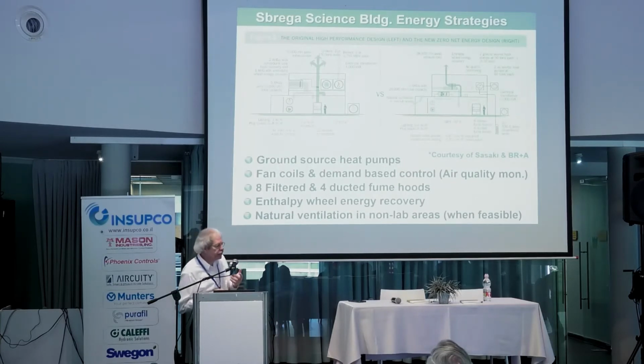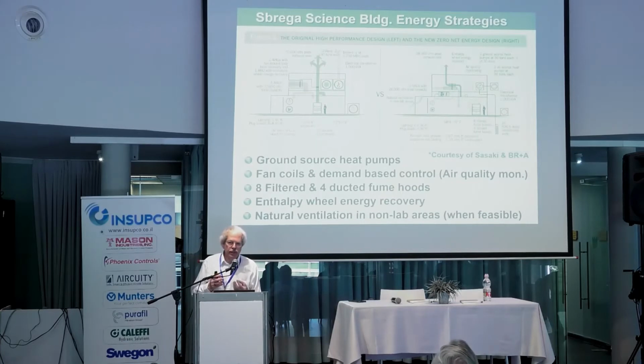They also used an enthalpy wheel on the general exhaust. You're not going to take contaminants from a fume hood and put them through an enthalpy wheel—you only use it for the cleaner air from general room exhaust. But that can be helpful, and you can see that here.